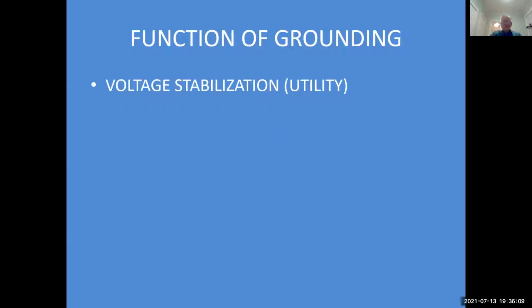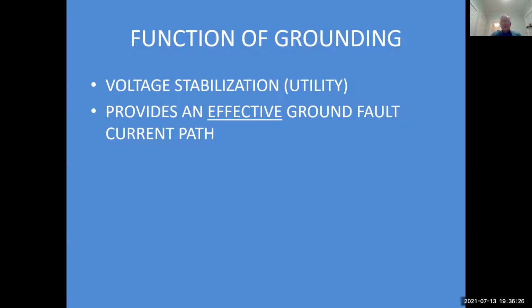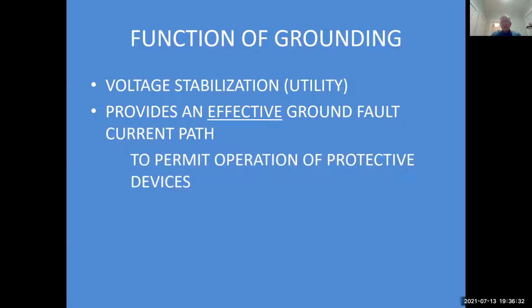The reason we ground is voltage stabilization from the utility viewpoint. It provides a more stable supply. Some European countries have ungrounded systems. In the United States, we have grounded systems referencing earth ground for the power coming into the house. Grounding provides an effective ground fault current path under fault conditions, which permits operation of protective devices.